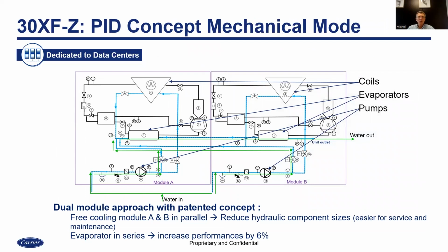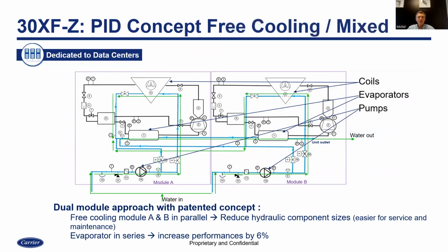Yeah, so when we are in mechanical mode, in the free cooling mode, basically water enters, in both sides is the same. And this valve is closed, this one is open. So water first will go through hydronic coils, which will benefit from lower ambient temperature. Then water returns and comes back to this point, and then if needed, additional cooling will be made.